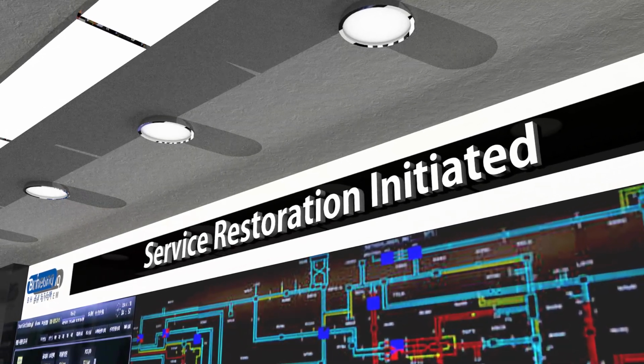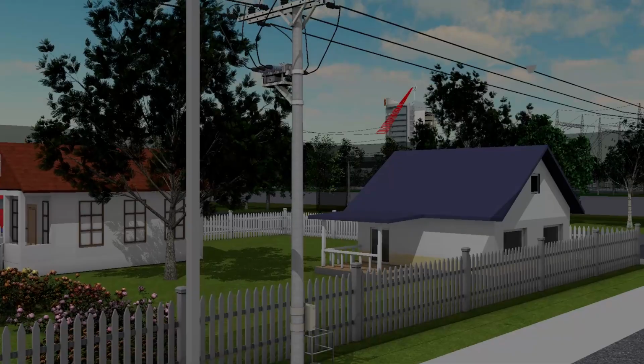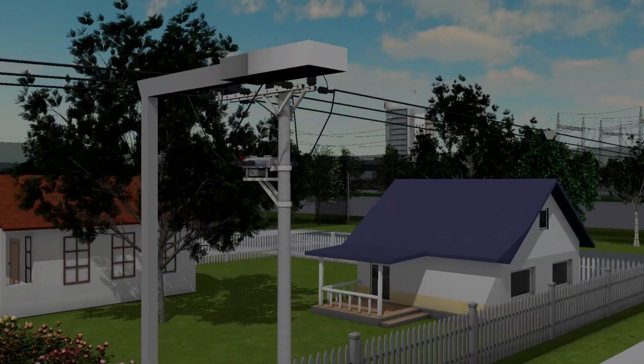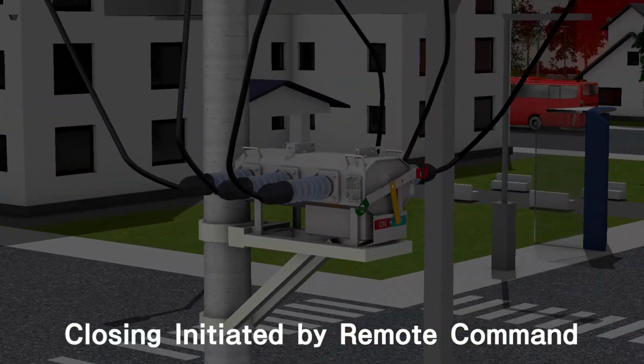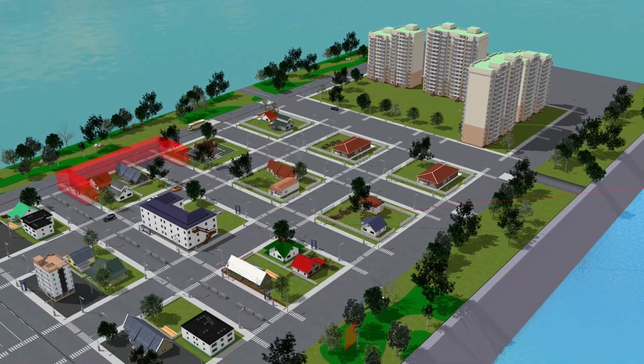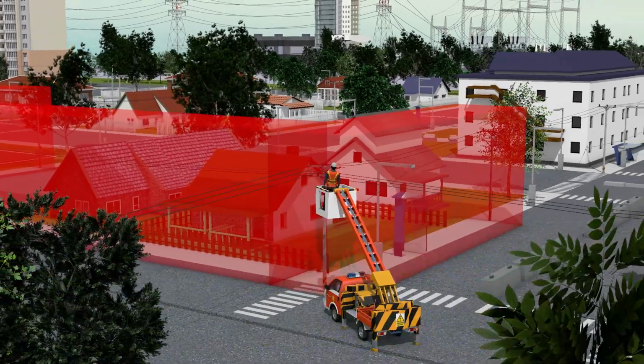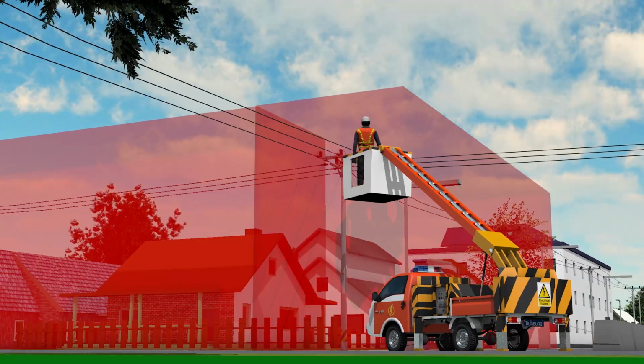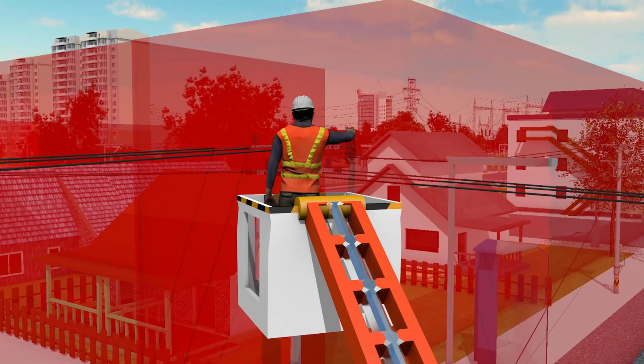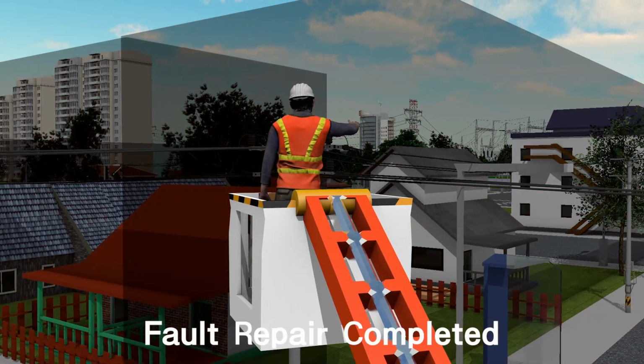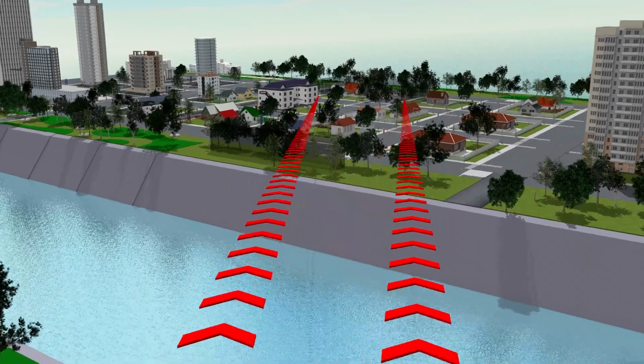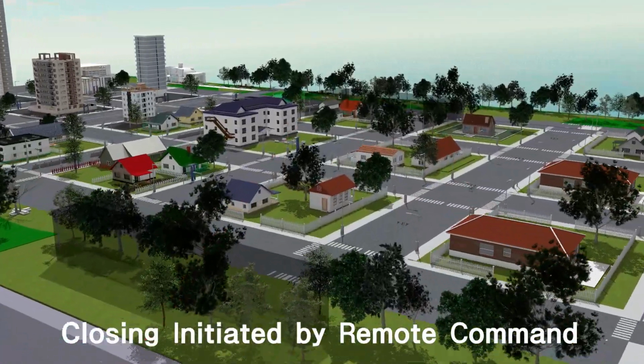After the faulty section is isolated from the system, the Distribution Control Center remotely closes the load break switch, which normally is open, resuming the power supply to the healthy section where the power outage occurred. After the measures against the faults on the line are completed, each equipment will be controlled on-site or remotely to return to a normal network configuration.